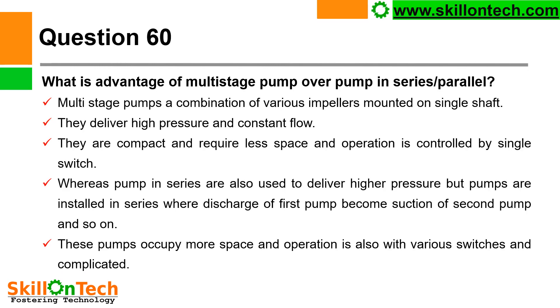Question 60: What is the advantage of a multi-stage pump over pumps in series or parallel? Multi-stage pumps combine various impellers mounted on a single shaft; they deliver high pressure and constant flow, are compact, require less space, and operation is controlled by a single switch. Pumps in series are also used to deliver higher pressure, but each pump is installed separately where the discharge of the first pump becomes the suction of the second, and so on. These occupy more space and require various switches and more complex operation. Therefore, where high pressure is needed, multi-stage pumps are preferred over pumps in series.